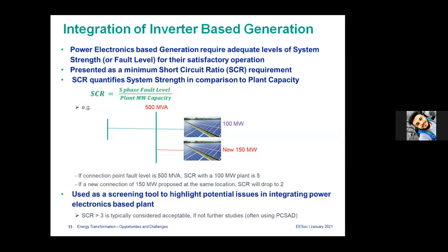And so what's the issue with integrating power electronic generation? Most power electronic generation, such as solar farms and wind farms, are grid following inverters, relying on inverters to connect to the AC networks. But they rely on the grid for correct operation. Inverters have a phase lock loop that relies on the system voltage profile for satisfactory operation. So if you have a low fault level location, the grid voltage can change significantly for disturbances, and the inverter struggles to maintain stable operation.